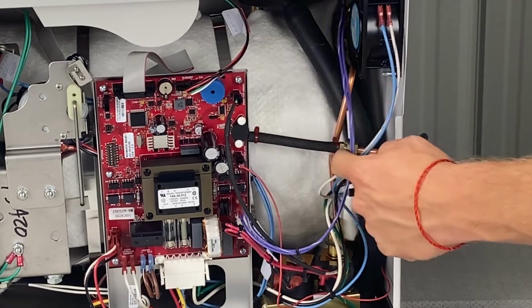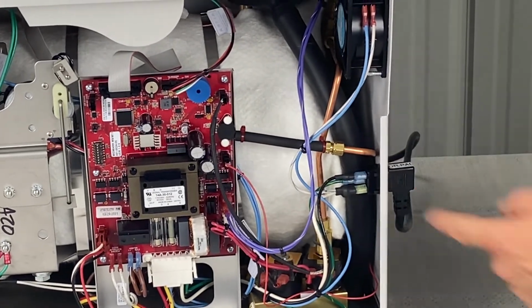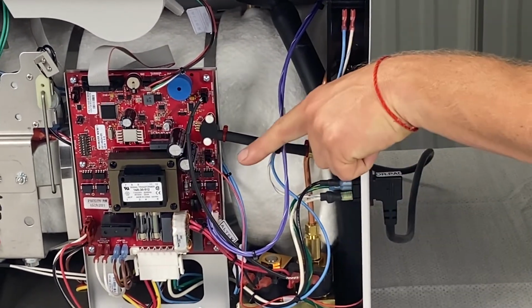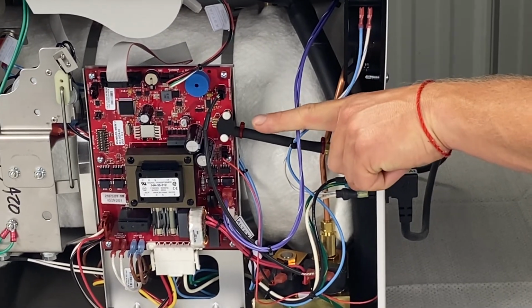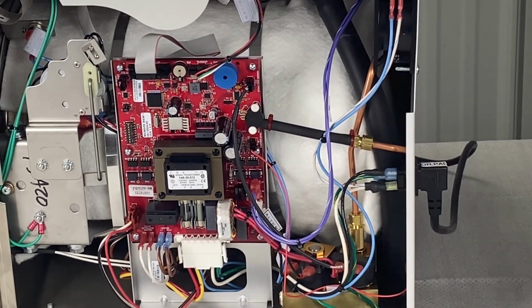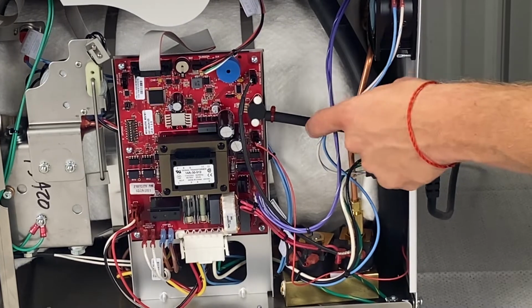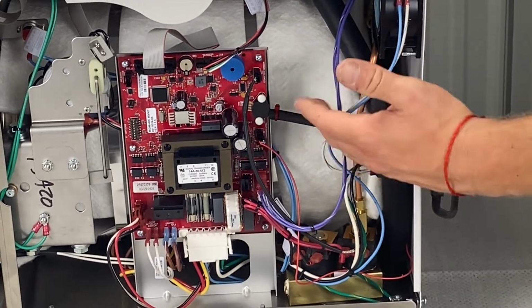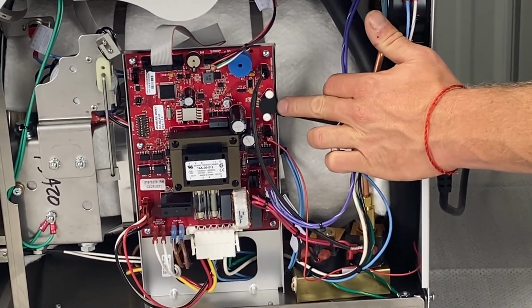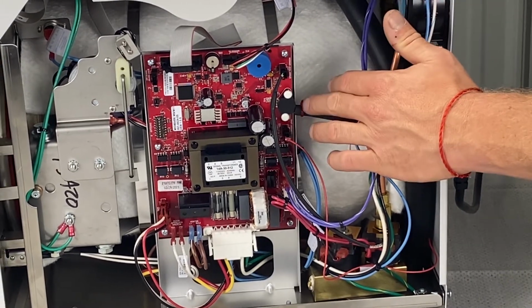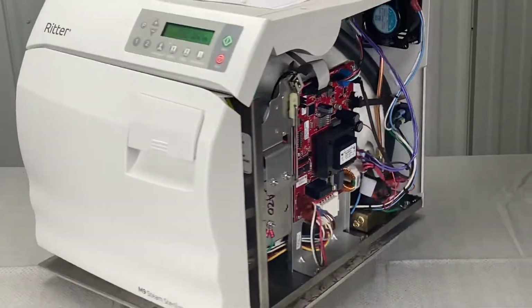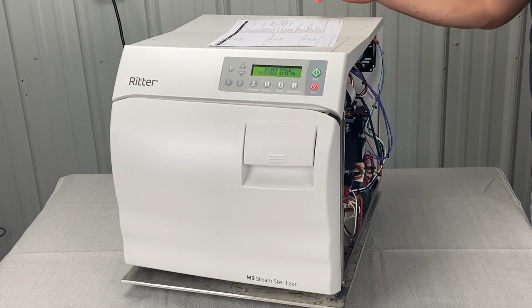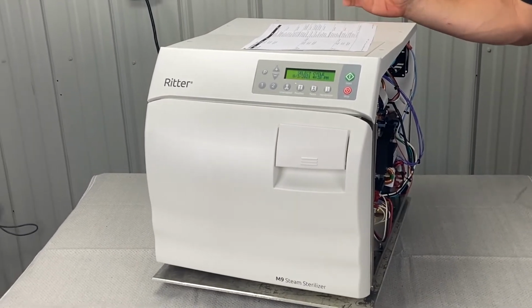Also, the positioning is very key. You've got to leave it in this position. It should not be pointing down that way. Horizontal is okay, and I wouldn't say that that's causing all the errors, but then we will adjust it to here. That's because this is what reads the steam, converts it into an electrical signal, and shows you on the screen here. So, okay, that's pretty much it.